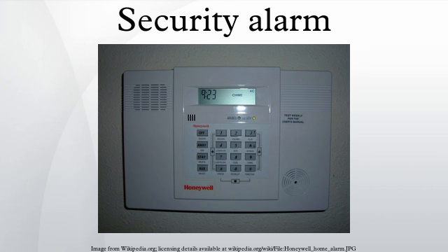Wireless monitoring of the alarm system protects against a burglar cutting a cable or from failures of an internet provider. This full wireless setup is commonly referred to as 100% wireless. Hybrid systems use both wired and wireless sensors to achieve the benefits of both. Transmitters, or sensors, can also be connected through the premises' electrical circuits to transmit coded signals to the control unit. The control unit usually has a separate channel or zone for burglar and fire sensors, and better systems have a separate zone for every different sensor, as well as internal trouble indicators.